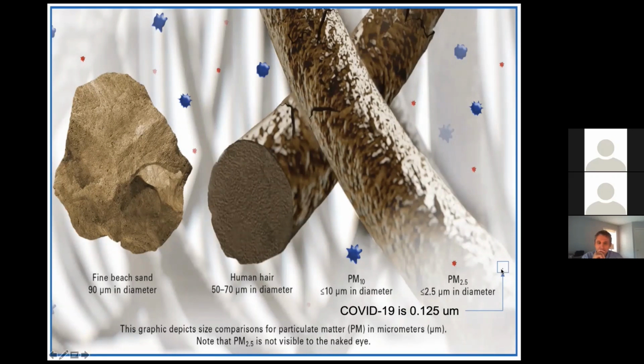So COVID-19 is 0.125 microns, but with COVID, when you cough and sneeze it out, it's generally covered with mucus. And so it's a lot larger, it's heavy, and it drops out of the air fairly quickly. But now they're finding that, especially in lower humidity environments, less than 40% humidity, the mucus that surrounds it can evaporate rather quickly as it's settling to the floor, and that leaves the virus exposed to stay in the air a lot longer. And according to ASHRAE's infectious aerosol paper, the smaller the particle, especially in a room with no air movement, the longer it's going to stay in the air. So a 0.5 micron particle can stay in the air for 40 hours or more with no air movement.